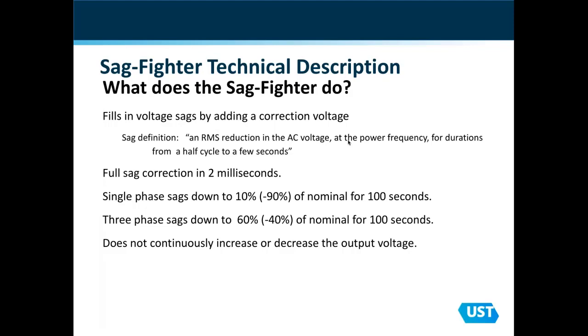It makes that full correction within 2 milliseconds. So it's obviously a very fast responding device, and it can correct a single phase sag down to 10% remaining voltage, or a full 3-phase sag down to 60% remaining voltage. So it corrects for deeper sags in voltage than the Surevolt voltage regulator. So 2 different applications, really.